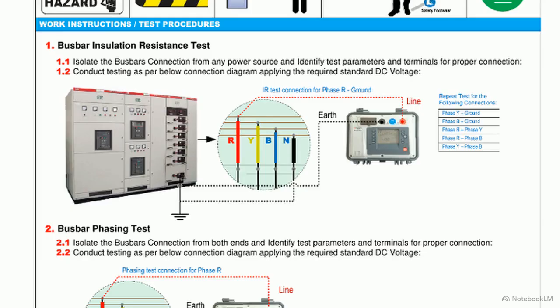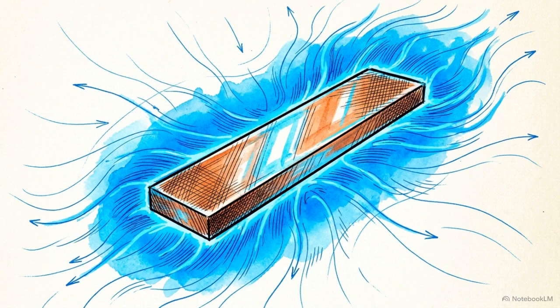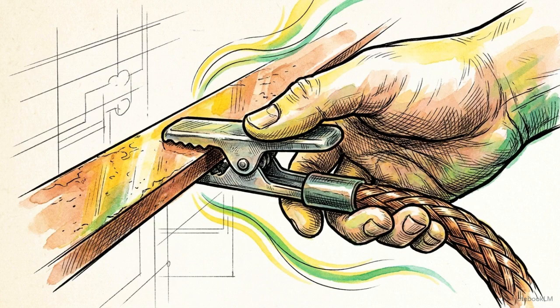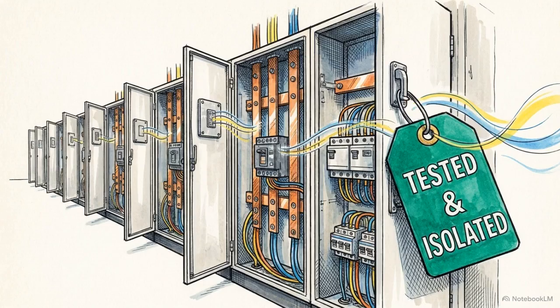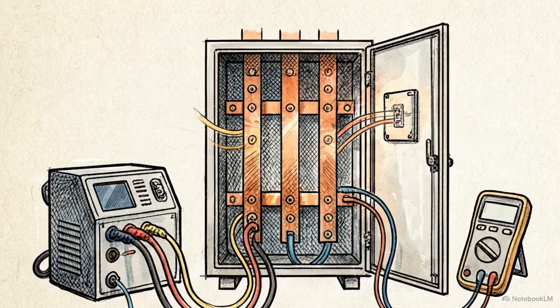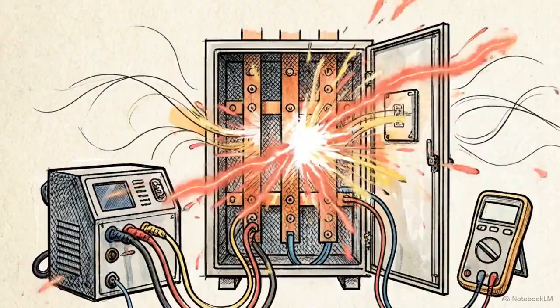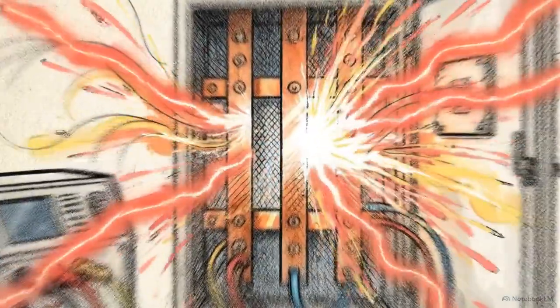This schematic shows the insulation resistance test setup. A targeted DC voltage is applied from the phase R terminal directly to earth ground. Engineers verify high resistance, confirming intact insulation, then record phase Y and phase B to ground vectors. Because insulation resistance testing applies high voltage, the busbars act like capacitors and store electrical energy. Engineers must actively discharge every busbar to earth immediately after the test concludes to prevent shock. Confirming this baseline physical isolation ensures the copper paths are secure. Without this step, injecting voltage to test the control logic later could short out adjacent components and cause severe damage.